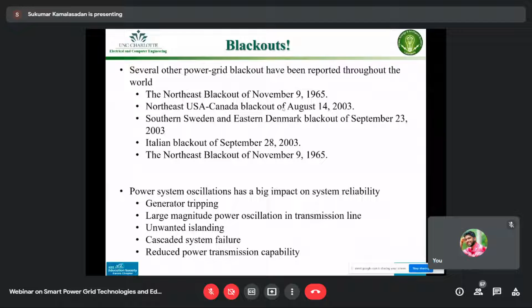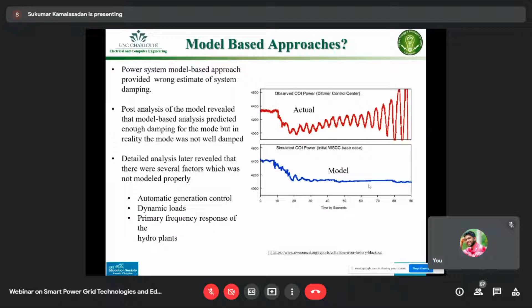In order to monitor, first we wanted to make sure these oscillations we're seeing are actual, not artificially created. There's a difference between the real actual oscillation and what you see in a model if you're not using a phasor measurement unit. The real oscillations look like this, but the model says there's no oscillation, because we aren't able to capture those dynamics or changes fast enough, and also can't model it properly.